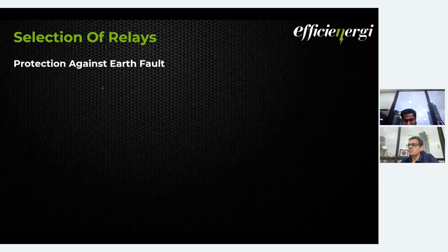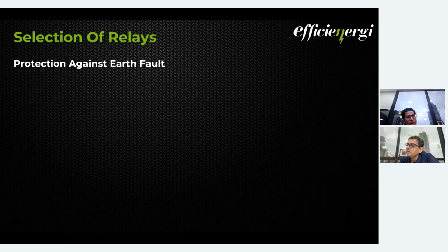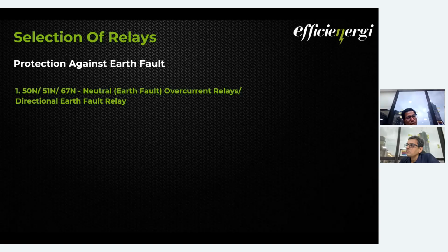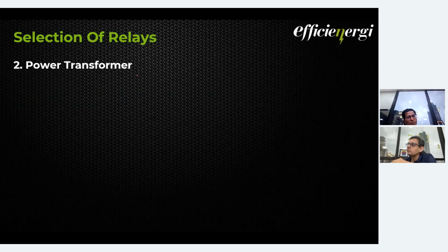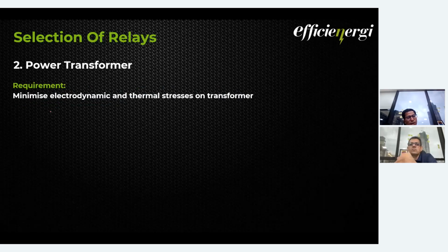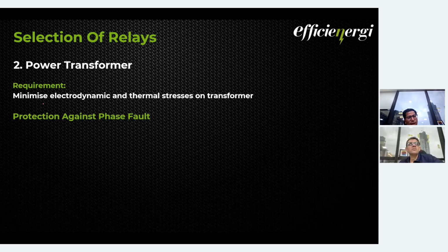Then, sorry, protection against earth fault. Here again 50N, 51N, 67N. With respect to earth fault protection and earth fault requirements, for power transformers, the requirement is to minimize electrodynamic and thermal stresses on the transformer, and protection against phase fault.